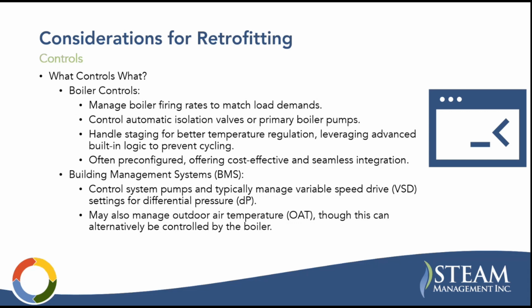And of course, it's easier to let the boiler control those so that it all works smoothly. Letting the boiler handle the staging so that the boilers are operating at their optimized levels. They communicate really well together. They're generally designed to be installed in a modular way so that they're operating together. And so you can let the boiler controls take care of that. And it's often pre-configured and it's more cost effective and kind of seamless integration.